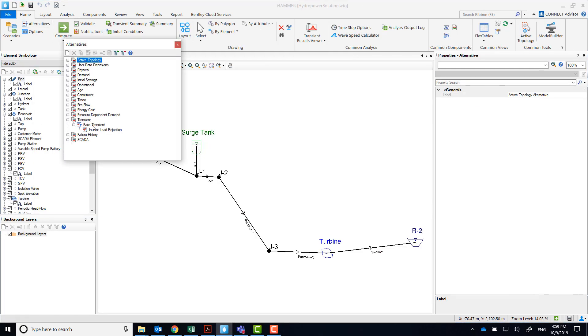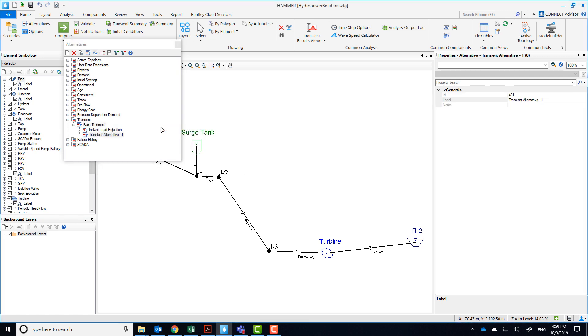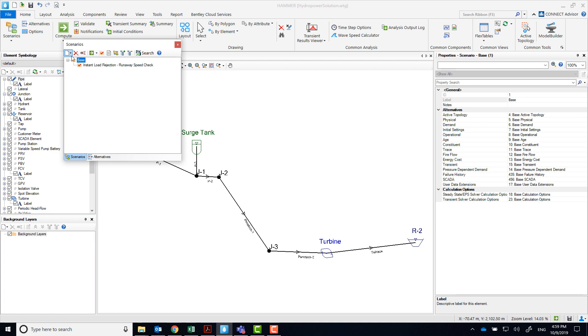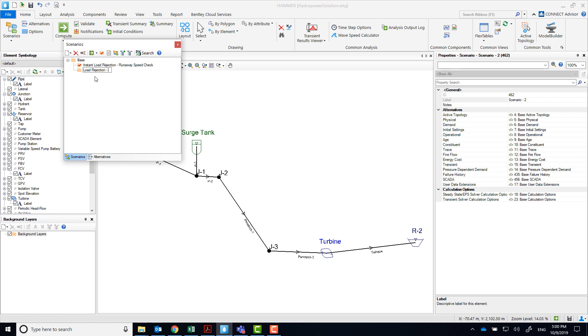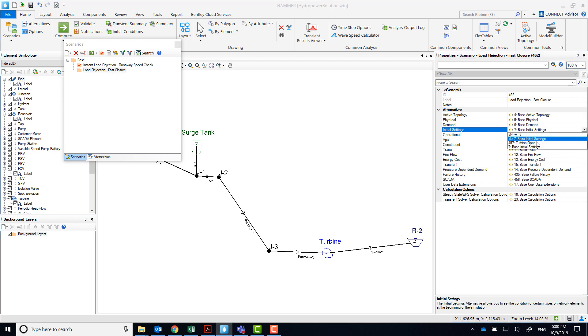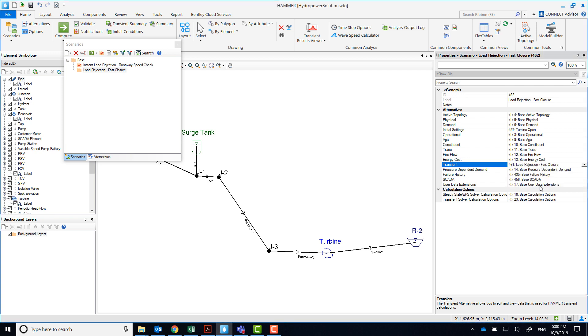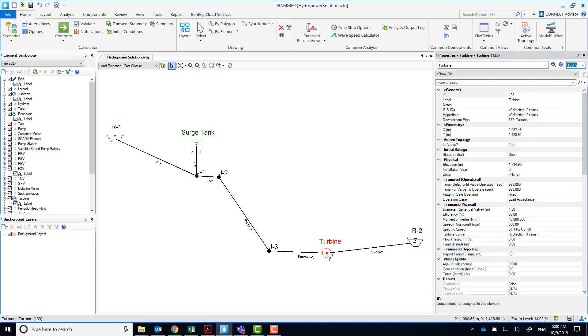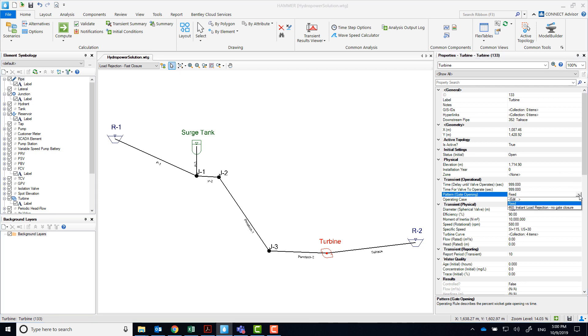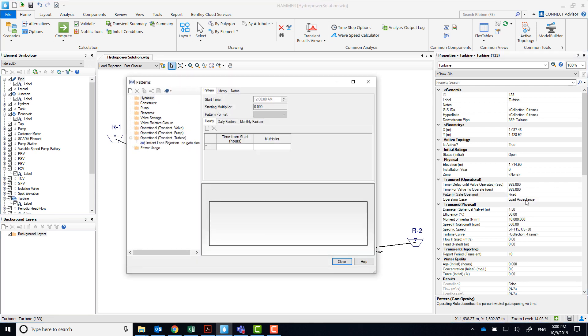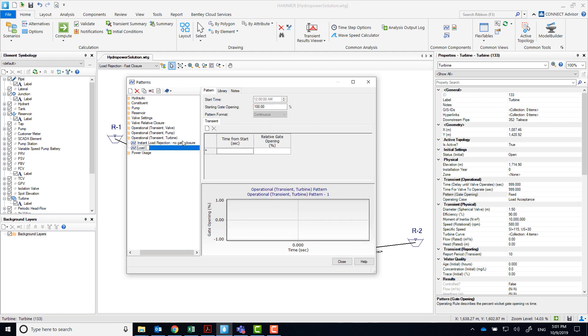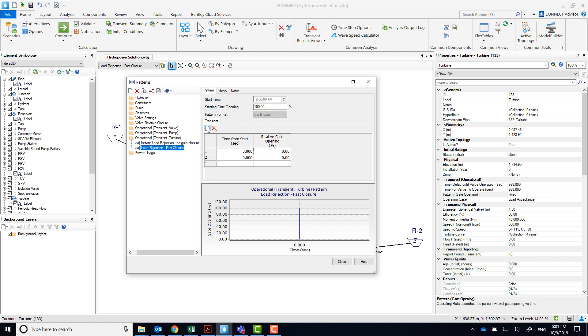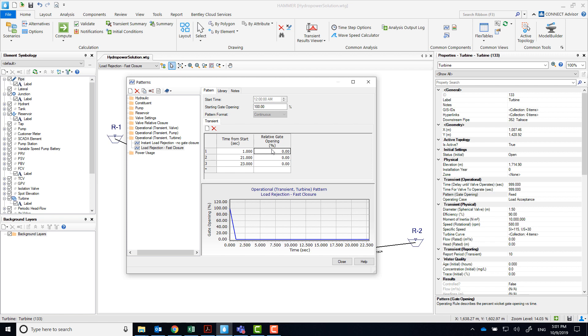Let's create the Load Rejection Fast Closure Run. This usually results in the most severe transient pressures. Create a new transient alternative and a new scenario. Make sure you assign that new transient alternative and initial settings to the new scenario. Make sure your current scenario is Load Rejection Fast Closure and create a new gate pattern. For this run, we're going to consider that the electrical load is rejected at 20 seconds and that the wicket gates will start closing at 21 seconds. It will take 2 seconds to completely close the wicket gates.